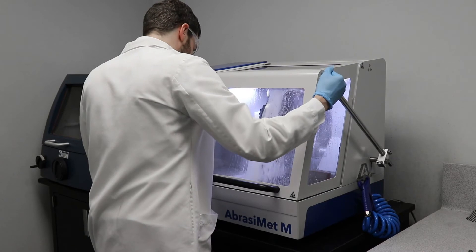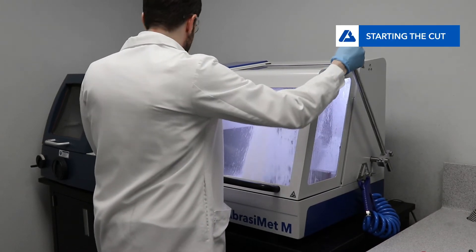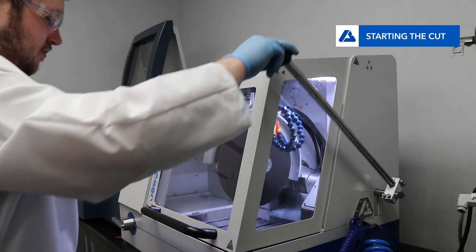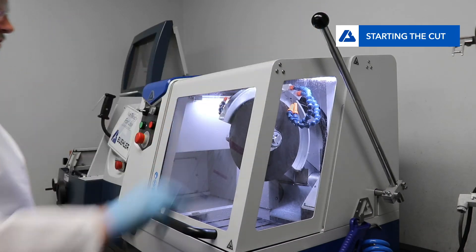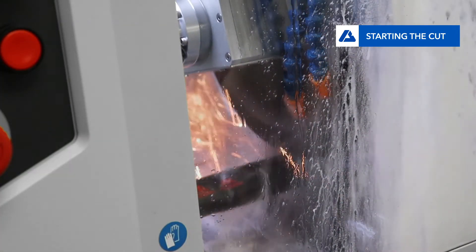Press the green start button to turn on the motor. Grasp the cutting handle and bring the blade down onto the part. You'll notice how light the cutting arm is compared to a typical manual sectioning machine, because the motor on the AbrasiMet M is not positioned on the cutting arm. This is in an effort to reduce user strain.